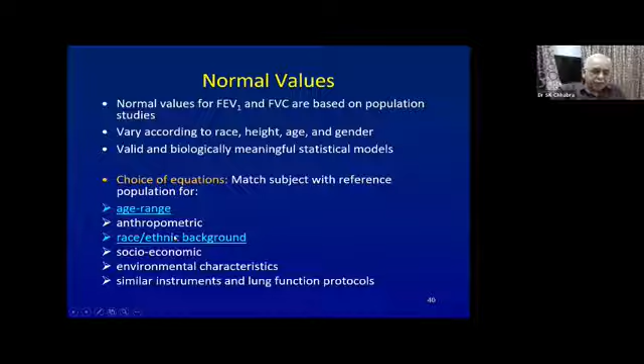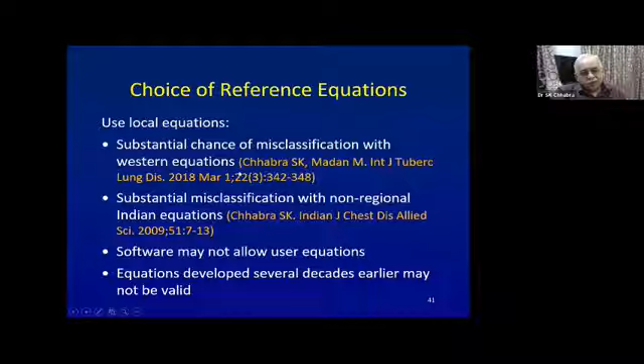We must use equations which match the patient's ethnic background, and they should apply to the patient's age range as well. We must use local equations because there is a substantial chance of misclassification when Western equations are used, because Caucasian values are larger than Indian values, and even within different regions in India we have found that there are regional differences. So ideally you should have your own equations for your region. They should be current equations developed as per the current standardization protocols, because the equations developed earlier, and we have several equations from different regions in India developed 30 or 40 years ago, may not be valid. A good software will allow you to feed in your own equations.